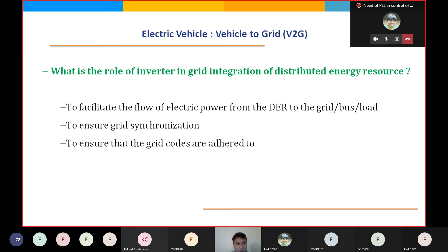It has to ensure grid synchronization. Your PLL can detect and provide it the signals or data, but the inverter is the one which implements grid synchronization. At the same time, the inverter ensures that grid codes are adhered to. So for this, when we talk about adherence, synchronization, or control of flow of power, voltage oriented control is employed.